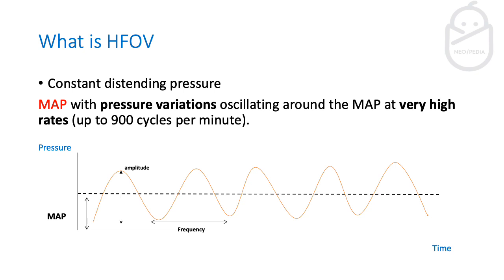So what is high frequency oscillation? Basically it's a constant distending pressure. You're giving a continuous MAP with pressure variation oscillating around this MAP at a very high rate, which can reach up to 900 cycles per minute. As you can see in the graph, the dotted line represents the continuous MAP, with waves oscillating around it. The height of the wave is what we call amplitude, and the frequency is how many cycles per minute we're giving.